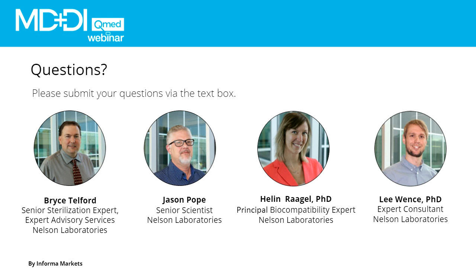And this next question is either for Jason or Bryce. Some of the VHP recipes include plasma steps. In your experience, have you seen any adverse effects on materials, polymers in particular, relating to the plasma step? I have not. Yeah, I would just say I've not seen any adverse effects because of that additional step built into particular models of VHP sterilizers. Sure.